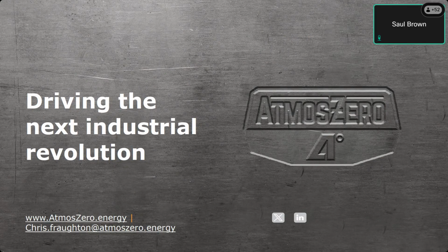There was mention that a turn-down rate below 70% further reduces COP. Can you give a rough approximation of the percentage reduction in COP? Yeah, it's pressure dependent, so it's a little tricky, but just to ballpark it, down to 70%, you generally don't have any COP hits. Between, call it 50 and 70% turn down, you're starting to approach 1.1, 1.2. So it's a pretty significant hit in COP.